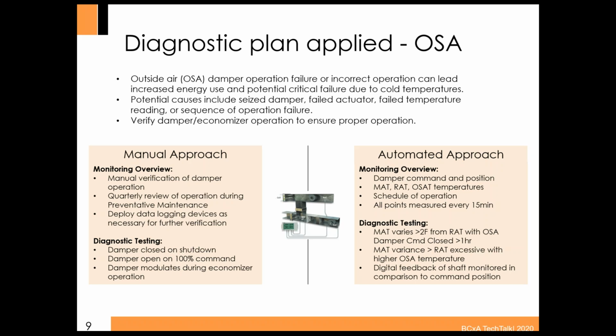So, from a diagnostic plan approach, just outlining a couple of points here. If you're doing a manual approach, thinking about that pneumatic system, we think about what we want to monitor there and what that looks like. It is a very manual verification. So it's using your operations and maintenance team members through preventative maintenance to do a check. And I mentioned quarterly here. That's a good reference point to ensure that you've got proper damper operation during the season changes. But it's also really dependent on how often you're seeing failures. If you've got a relatively stable system and you're not seeing issues, backing off to a semi-annual would be appropriate.